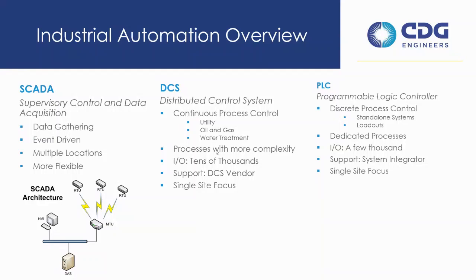The big difference between these three is really SCADA versus DCS and PLCs. Historically, SCADA is really a data gathering platform, as it says in the name - it's just pulling in information and displaying that typically on an HMI or maybe an annunciator panel. DCS and PLCs are more process control related, so they'll be a hardware and software solution, whereas SCADA is typically just a software solution.